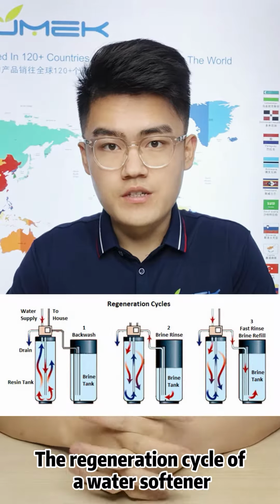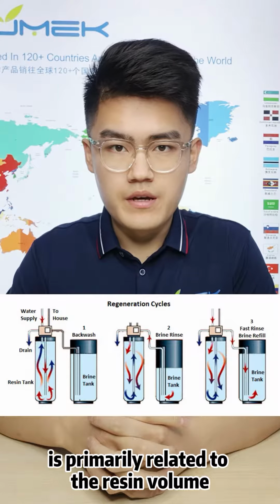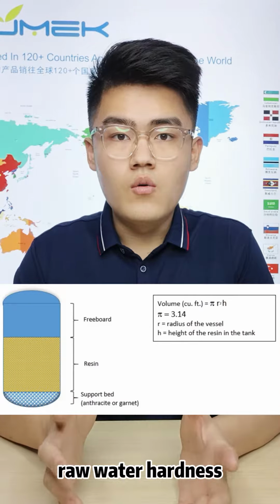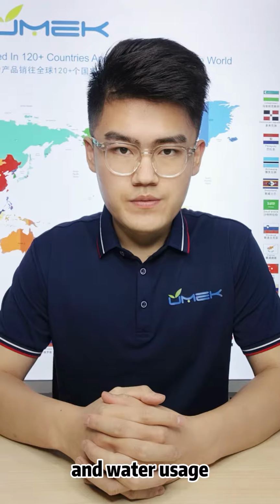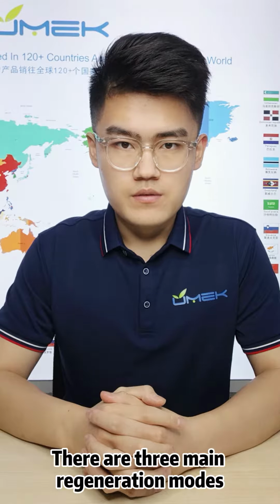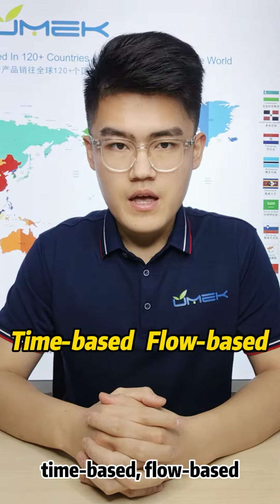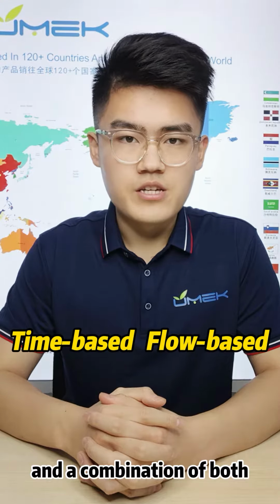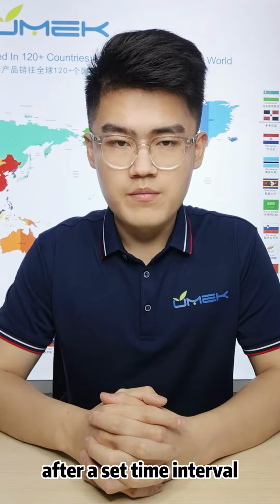The regeneration cycle of a water softener is primarily related to the resin volume, raw water hardness, and water usage. There are three main regeneration modes: time-based, flow-based, and a combination of both. In the time-based mode, the water softener initiates regeneration after a set time interval.